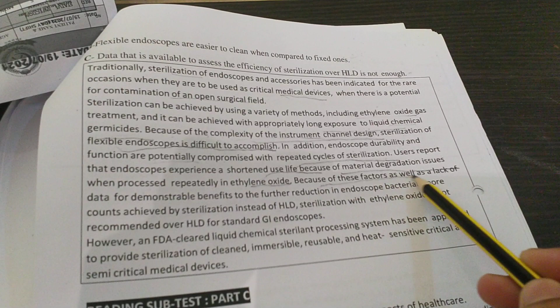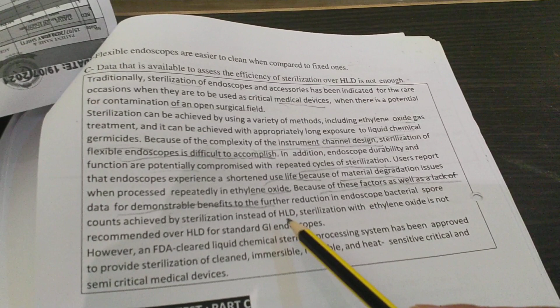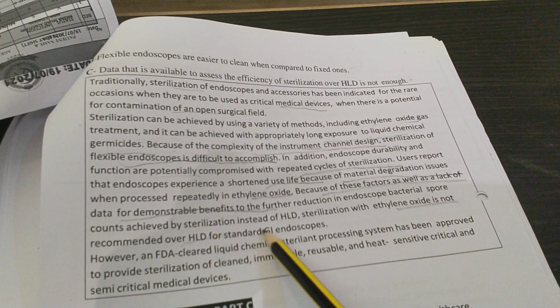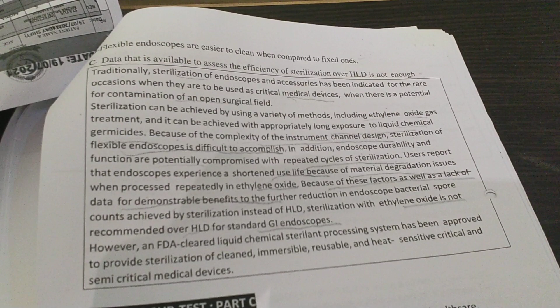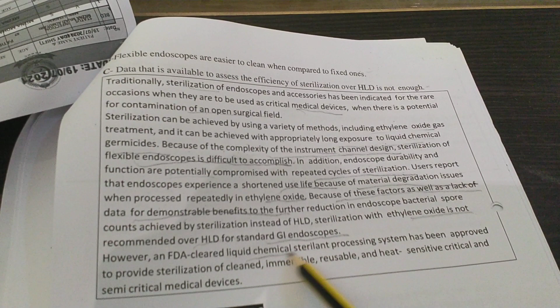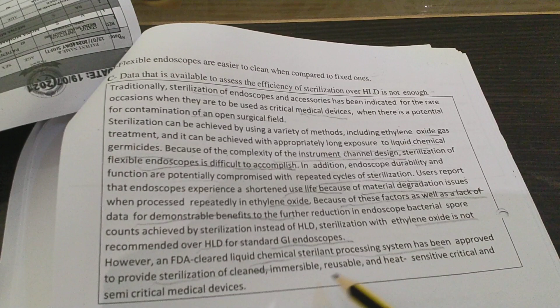It's spoiled easily. Then because of these factors, as well as a lack of data for demonstrable benefits to the further reduction in endoscope bacterial spore counts achieved by sterilization instead of HLD, sterilization with ethylene oxide is not recommended over HLD for standard GI endoscopes. There is no clear data; there is lacking data. However, an FDA-cleared liquid chemical sterilant processing system has been approved to provide sterilization of cleaned, immersible, reusable and heat-sensitive critical and semi-critical devices.